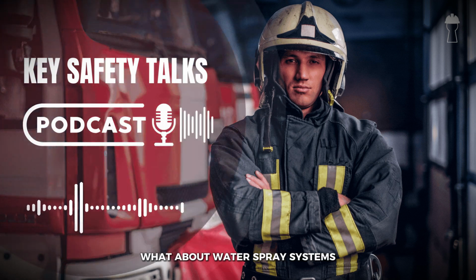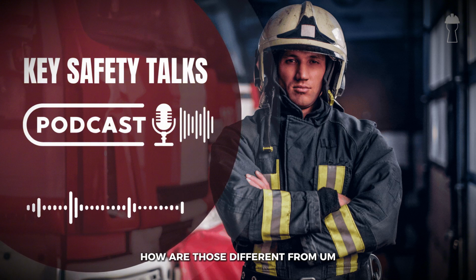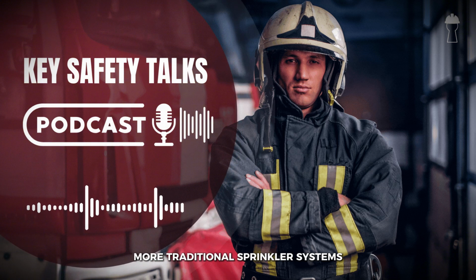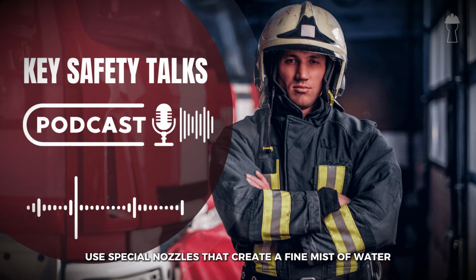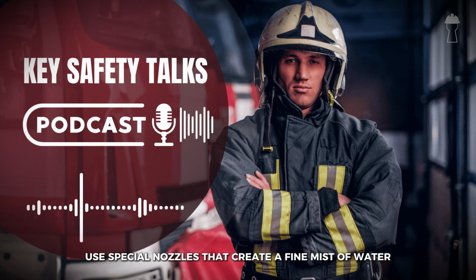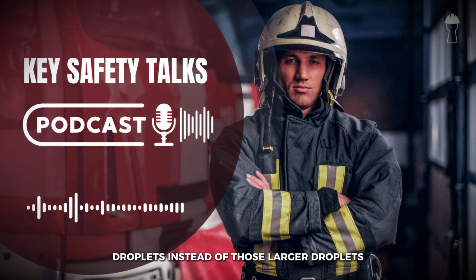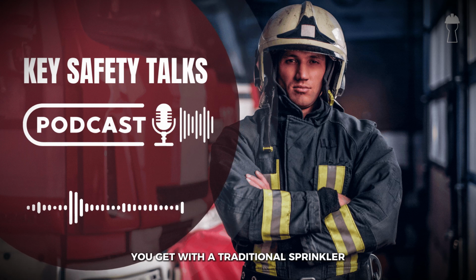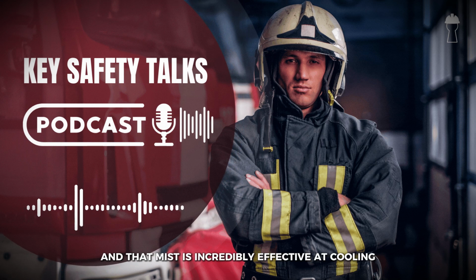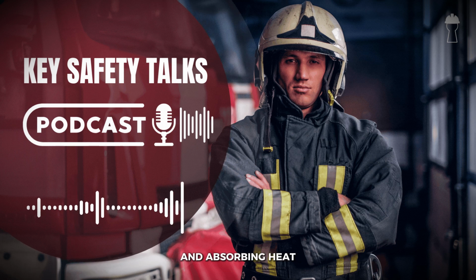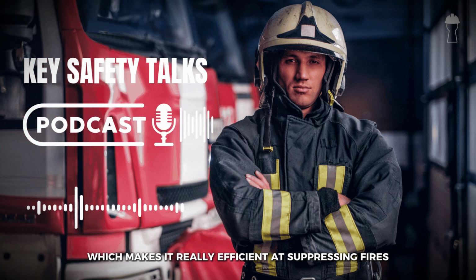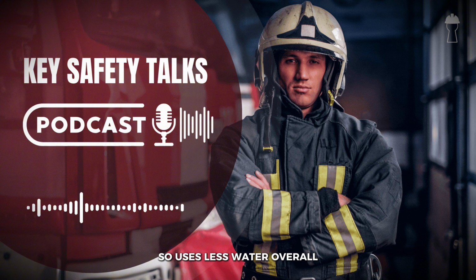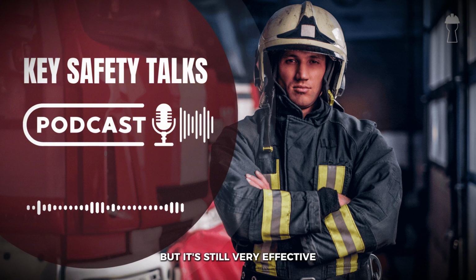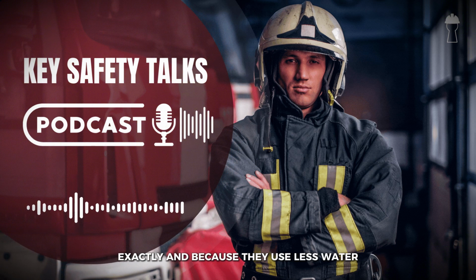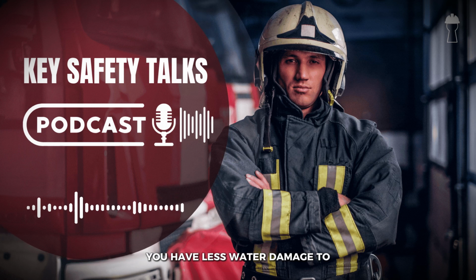What about water spray systems? How are those different from more traditional sprinkler systems? Water spray systems, they use special nozzles that create a fine mist of water droplets instead of those larger droplets you get with a traditional sprinkler. And that mist is incredibly effective at cooling and absorbing heat, which makes it really efficient at suppressing fires. So it uses less water overall, but it's still very effective. Exactly. And because they use less water, you have less water damage too. Okay, so it's a win-win.